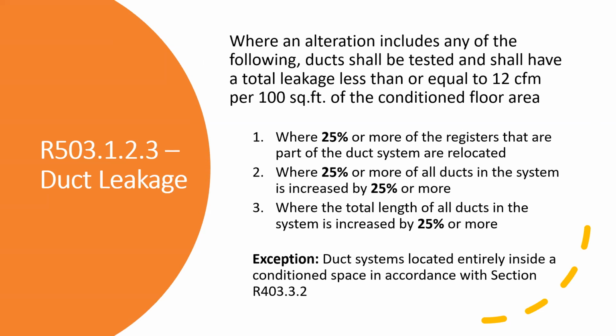So duct leakage, now they're talking about alterations. It includes the following: duct testing shall be required to be done. It's allowing 12 CFM per 100 square feet, not 4, not 8, in unconditioned space and in conditioned space. Now this says you're allowed 12 CFM per 100 square feet. But also it says where 25% or more of the registers that are part of the duct system have been relocated, you need to have it duct tested. Where 25% or more of the duct system is increased in size, you need to duct test it. Where the total length of the duct is also increased by 25%, it needs to be tested. Exception, though, is duct systems located entirely in the conditioned space.